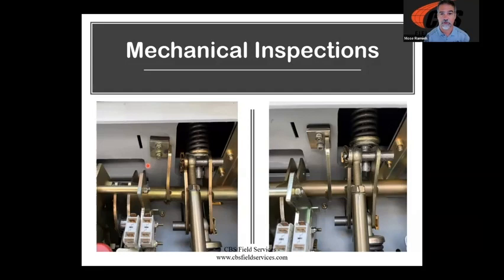But if you have a substation breaker, vacuum breaker in particular, go out there and look at the operator. Here's the operating rod, the drive rod link to close our contacts of our breaker. And what we'll notice is that this over travel arm has missed its bumper. See how it's just off to the right of the bumper there? Here it is in a non-damaged format, right? Well, in this damaged situation, where it's just off to the right, the breaker will not trip. It is over traveled and the mechanism is not in the right condition to allow the springs to release and open the breaker. That is a very hazardous condition, as you might imagine.